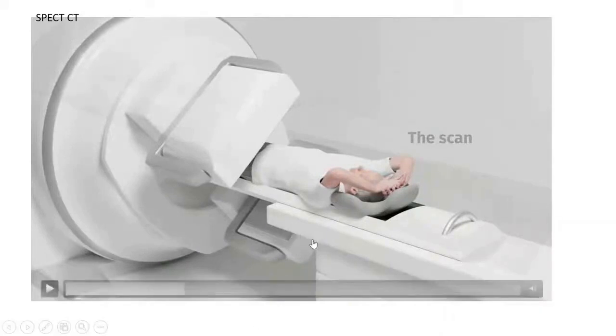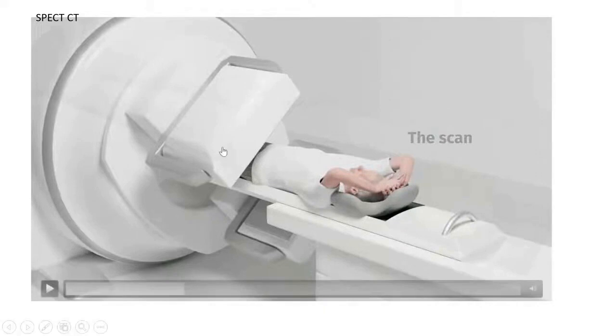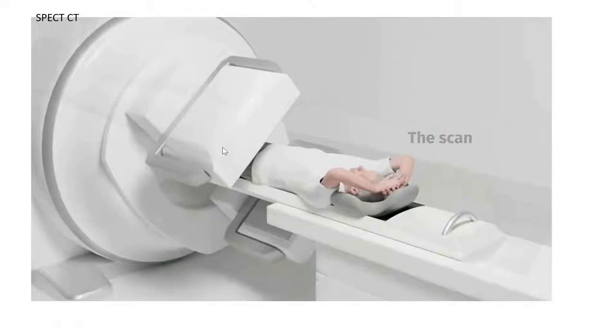The acquisition process occurs after I inject the patient, and the patient is prepared for the imaging process. The patient lies on the table or couch, and here I have the head. What is this head? This is the head that I use for detection. What am I detecting? I am detecting the gamma photons emitted from the patient. When I inject the patient with the radiopharmaceutical, this substance emits a type of radiation called gamma, which can be detected from the patient's body and reaches this head.